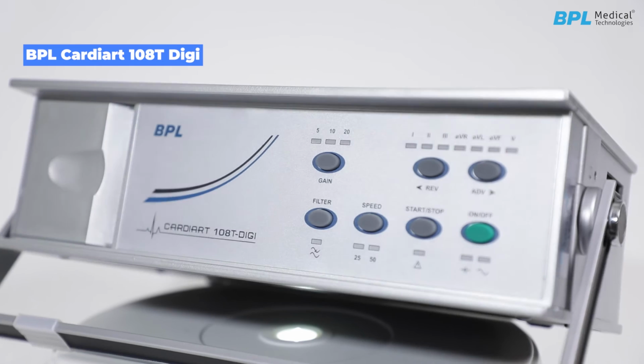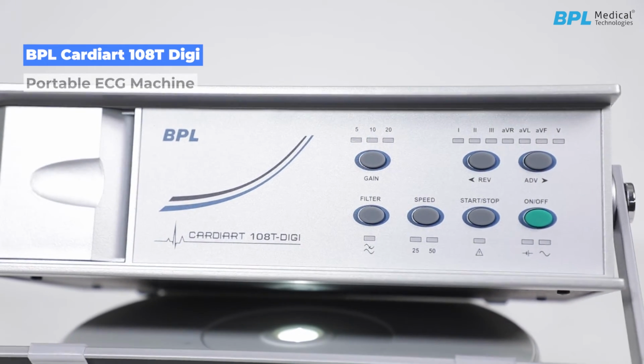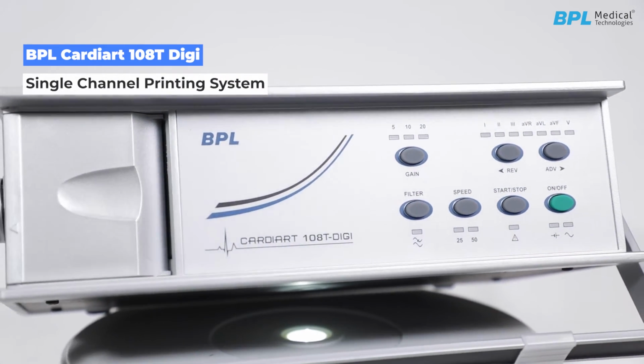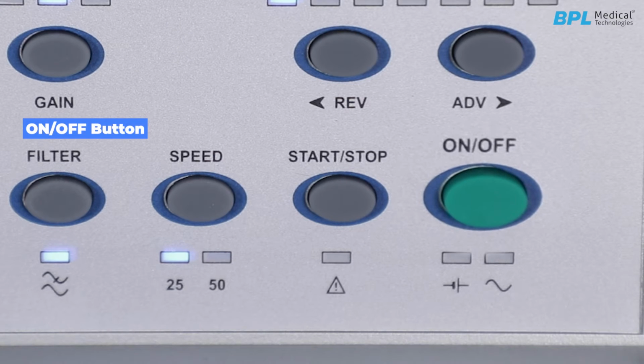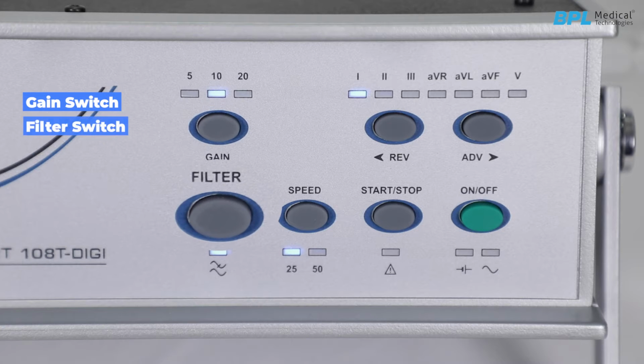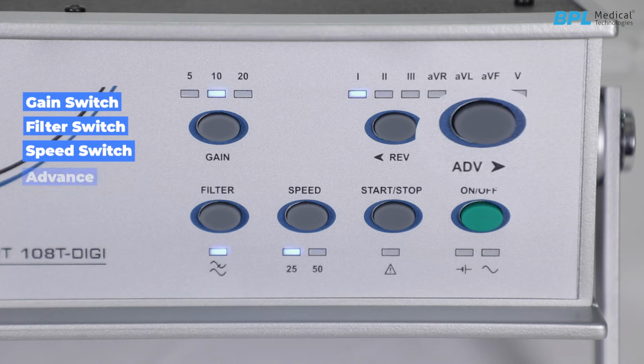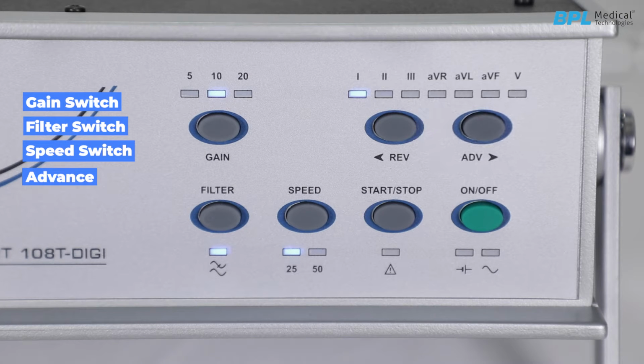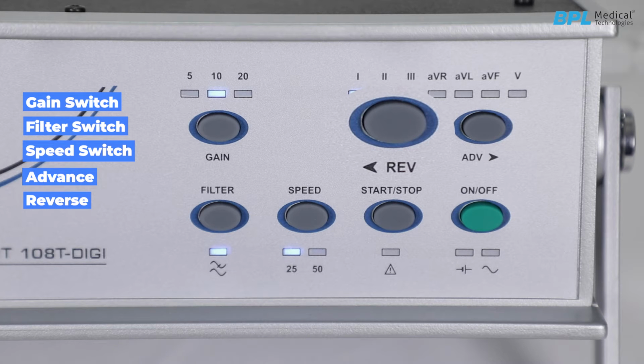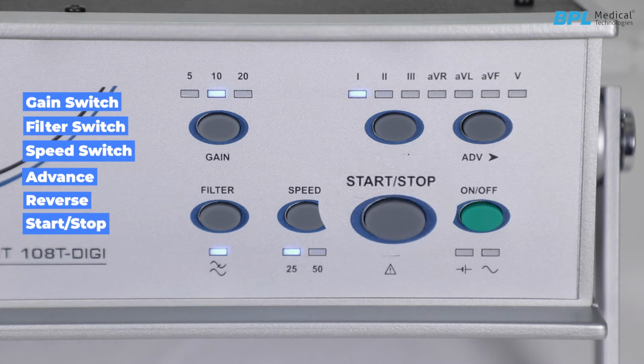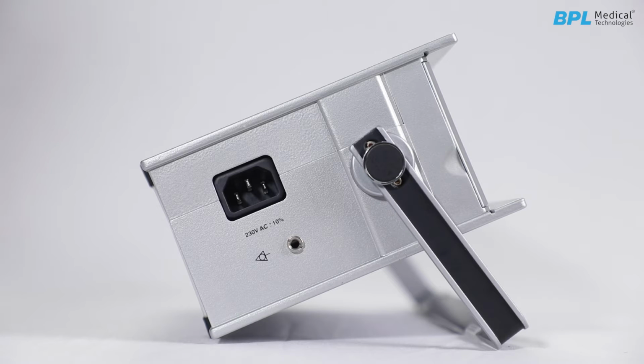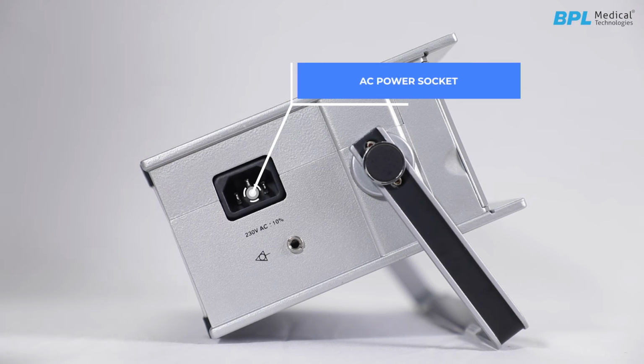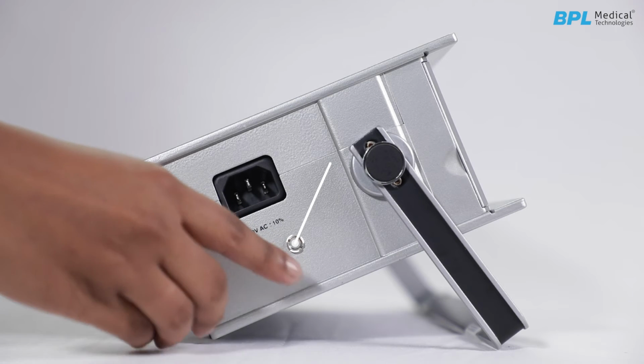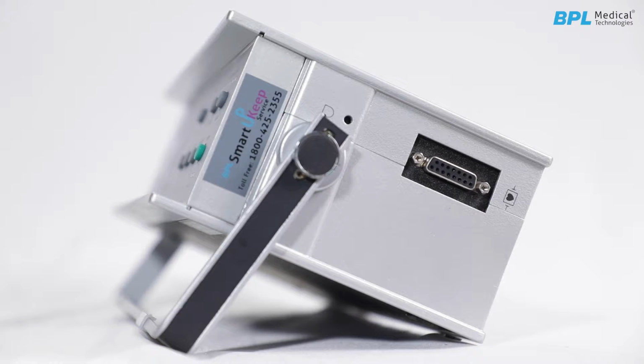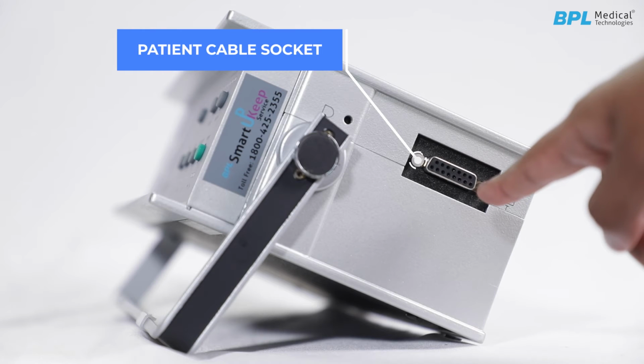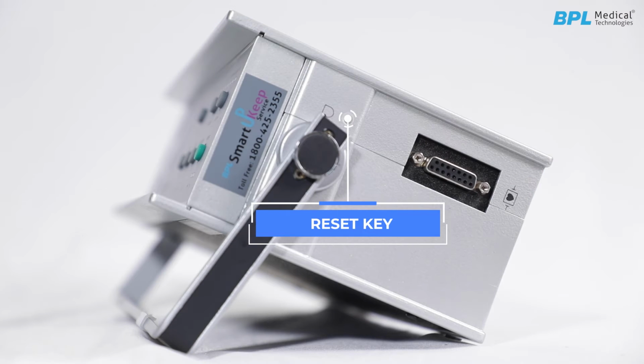Cardiart 108T Digi is a portable ECG with a single channel printing system. At the front panel, there is an on-off button, gain switch, a filter switch, speed switch, advance to select the forward lead and a reverse option to select the backward lead, and at the end you have the start-stop to print the job. At the right panel, there is an AC power socket and an equipotential ground. At the left panel, there is a patient cable socket and a reset key.